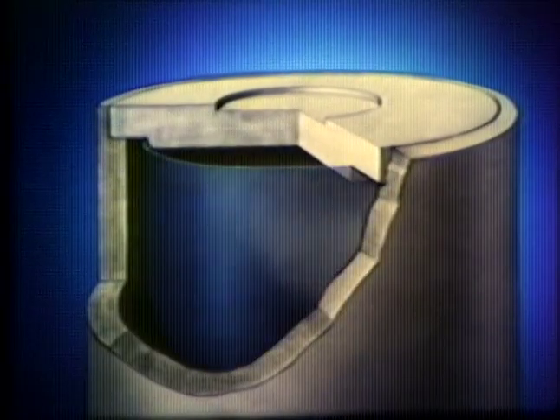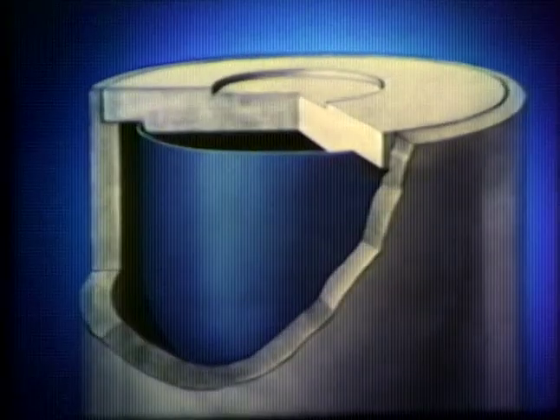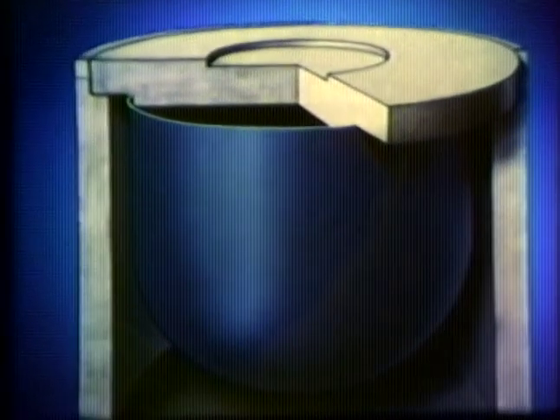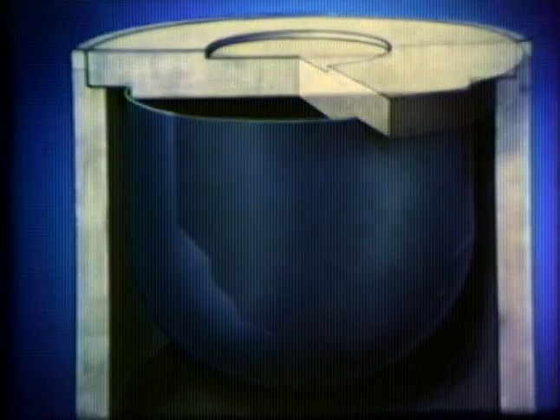Connected to this slab is the main containment vessel designed to confine the sodium. Its diameter is 21 meters. At the bottom is a support structure and a diagrid, which resembles a flat box and is used to position the reactor core and supply it with sodium. All around these structures is the giant funnel which separates the hot sodium area at the top from the cold sodium area at the bottom.